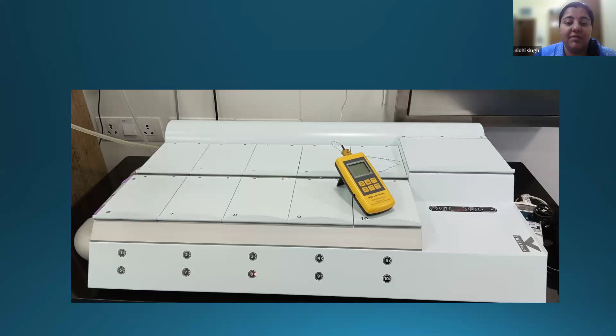Similarly, when we are testing the temperature on the stage, we do not test the temperature of the stage. We take a dish, keep the media in the dish, leave it for 20 to 30 minutes, and then check the temperature of the media. It is the media which should have a temperature of 37 degrees, not the stage. Next point, CO2 and O2 levels. They have to be checked on a daily basis. That is done by internal quality control. pH: now, pH is mandatory to check. This is especially important. I know many pH meters are costly devices and not available at multiple centers. So at least we should have a proper external audit team coming quarterly to check the pH.